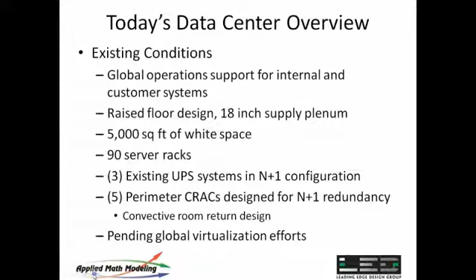Pretty typical, as you can probably imagine, in the sense that there were generations of cabling, both telecommunications and power. All the power distribution was supplied underfloor through floor mount PDUs that were also located in the data center, especially around the areas where the CRAC unit supply air was discharged. So we saw a lot of density of cabling underneath the floor, as well as generations of other interesting equipment that you find under any raised floor when doing an assessment - pretty typical of a raised floor that evolves over time and ends up with a derating of capacity in the systems because of all the infrastructure underneath the floor.